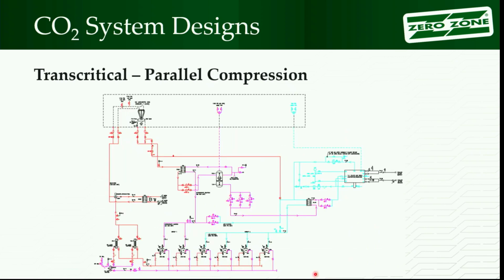And this is the larger system, happens to have parallel compressors on it. It's at the ice rink. This is the one I was embarrassed at, wondering where was the booster compressor. There aren't any. A couple parallel compressors sitting there though. Again, this is where you wind up with having some administrative controls. And again, you need to look at drawings because you don't know necessarily where you might pop into an administrative control situation and see what you got going on with them.